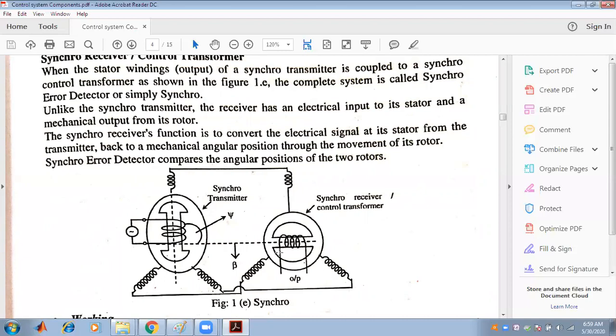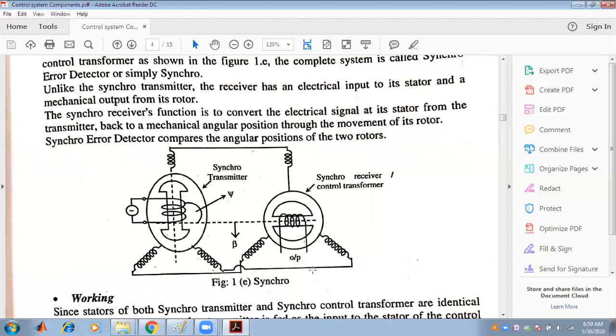Unlike the synchro transmitter, the receiver has an electrical input to its stator and a mechanical output from the rotor. The synchro transmitter converts mechanical angular displacement into an electrical output, which is then fed back to the control transformer. The synchro receiver's function is to convert the electrical signal back to a mechanical angular position through the movement of its rotor.